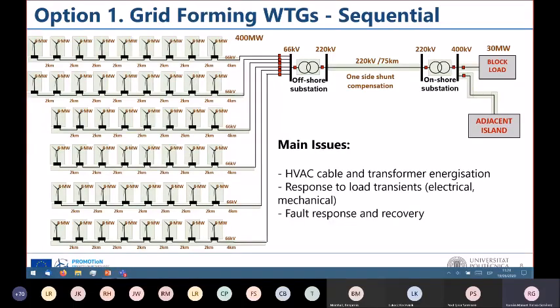And the third issue is fault response and mainly fault recovery. Fault recovery is quite important. Faults are much more likely to happen in this kind of unstable grid situation. And now, since the wind turbines are grid forming, they not only have to be able to do fault ride-through, but they are responsible for restoring the system after a fault. That's quite challenging when the grid forming is being carried out by a very large number of wind turbines.